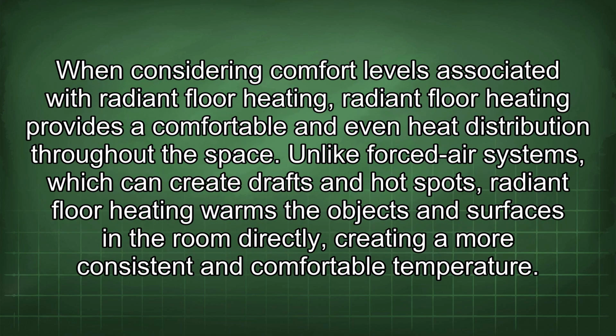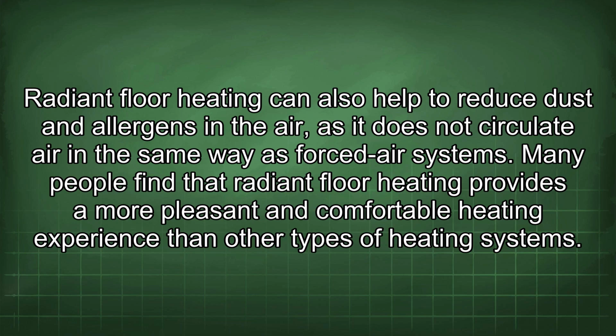When considering comfort levels associated with radiant floor heating, it provides a comfortable and even heat distribution throughout the space. Unlike forced air systems, which can create drafts and hotspots, radiant floor heating warms the objects and surfaces in the room directly, creating a more consistent and comfortable temperature. Radiant floor heating can also help to reduce dust and allergens in the air, as it does not circulate air in the same way as forced air systems.